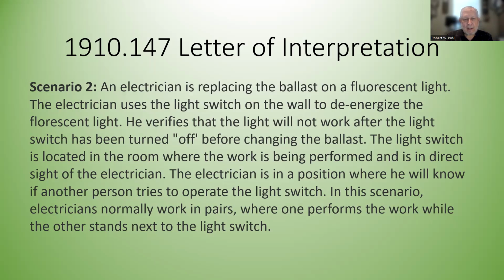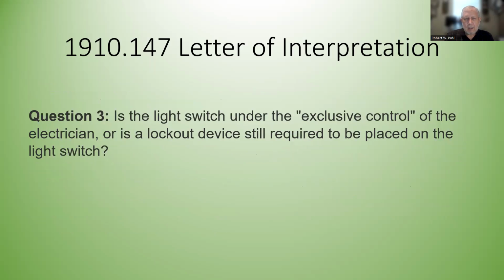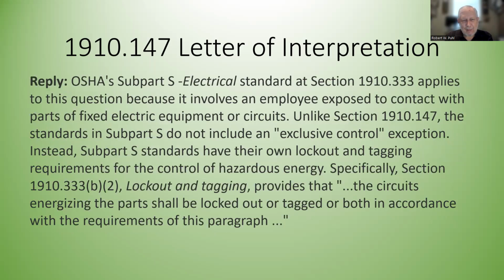The light switch is located in the room where the work is being performed, in direct sight of the electrician. The electrician is in a position where he will know if another person tries to operate the light switch. In this scenario, electricians normally work in pairs, where one performs the work while the other stands next to the light switch. Is the light switch under the exclusive control of the electrician? or is a lockout device still required to be placed on the light switch. Kind of already answered, didn't they?